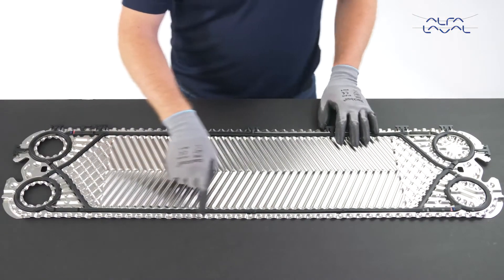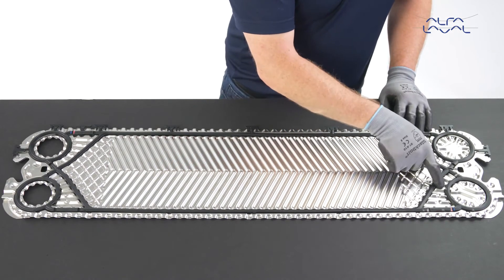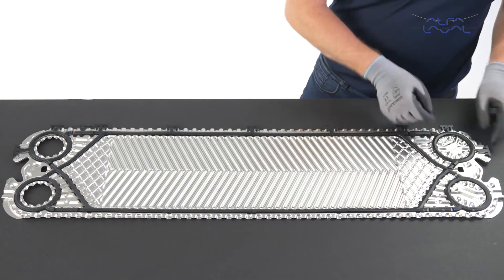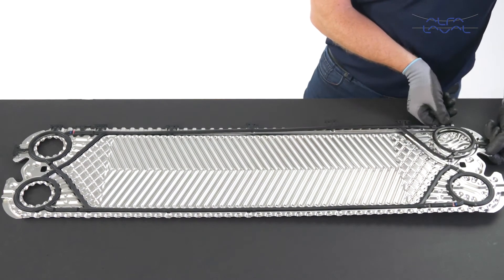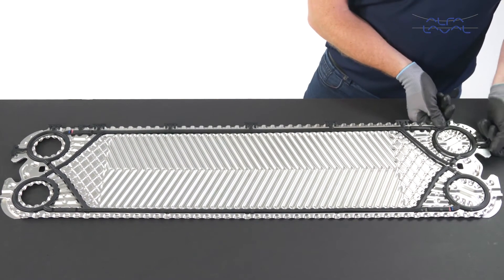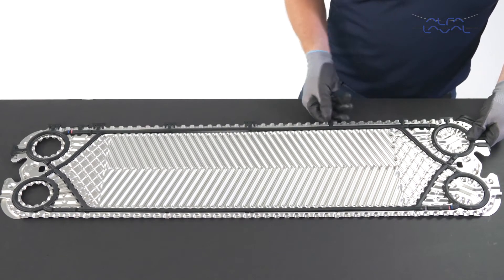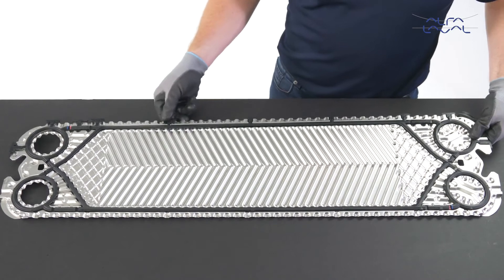The clips and connection beams must be removed on one of the halves. Tape the two halves of the gaskets that you cut together. We recommend that you use GC1 double adhesive tape. Remember, do not put any glue or tape in the ring gasket areas.